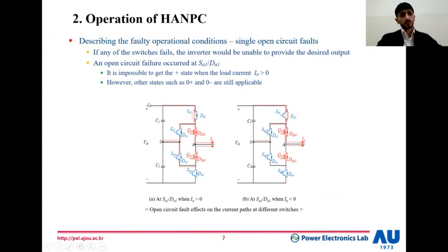Now, moving to the faulty conditions. Under the faulty conditions, the inverter is unable to provide the desired voltage. For example, in this case, we have an open circuit failure at the upper IGBT switch, SA1, DA1. In this case, it is impossible to get the positive state while the current is in the positive direction when you have an open circuit in the switch, or in the negative direction when we have an open circuit at the associated diode. However, the other states, such as negative, zero positive and zero negative are still applicable in this case.